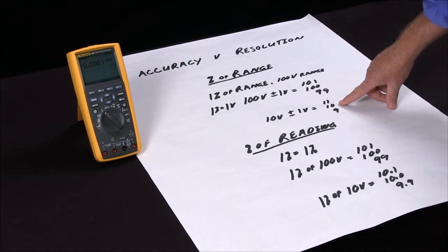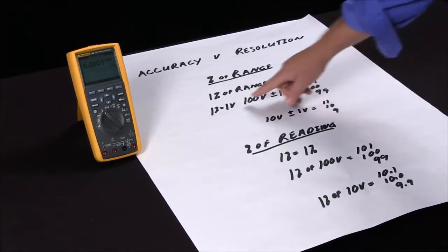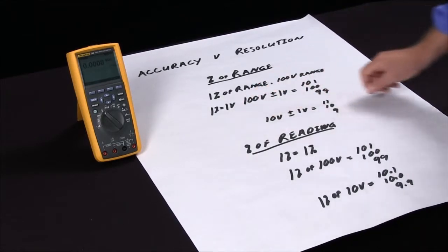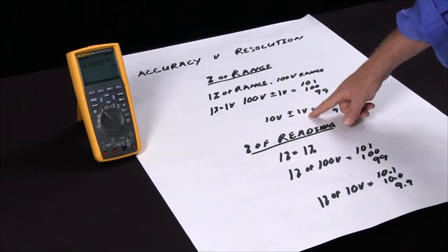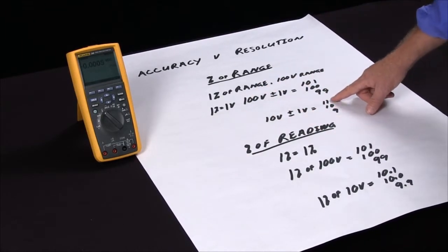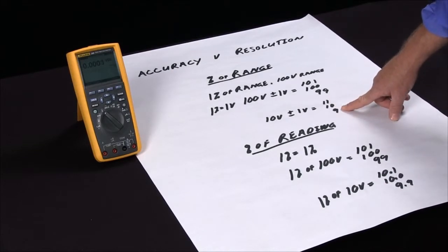But if we're measuring ten volts on this same meter, the one percent is plus or minus one volt. On a ten volt signal, plus or minus one volt will give us between eleven and nine, which is actually an inaccuracy of ten percent. So with percent of range, the accuracy actually decreases on the same range as you go down with the measurement values.